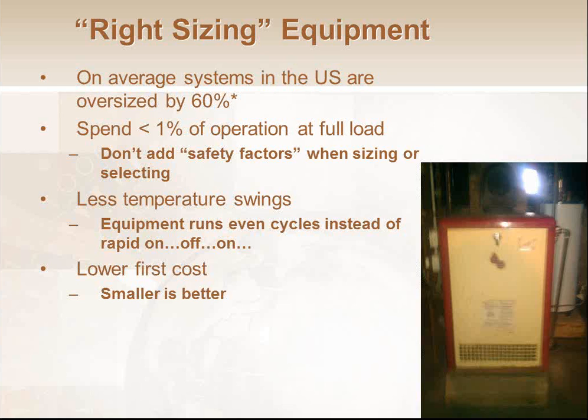It can't put out any more. And then we add them all up for the whole building. And if it comes up to say that we got 1.3 million BTUs radiator and we got a 2 million BTU boiler plant, where am I going to shove the other 700,000 BTUs even if I wanted to? I only got 1.3 of radiator.